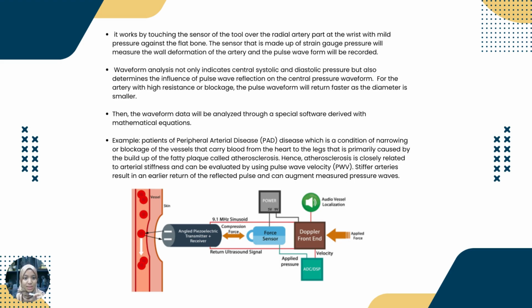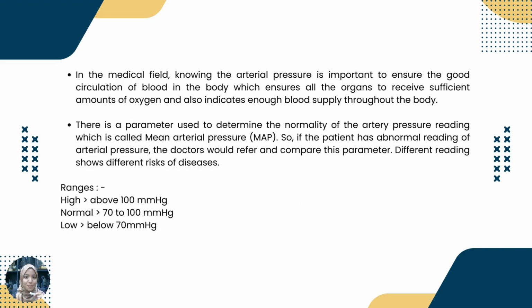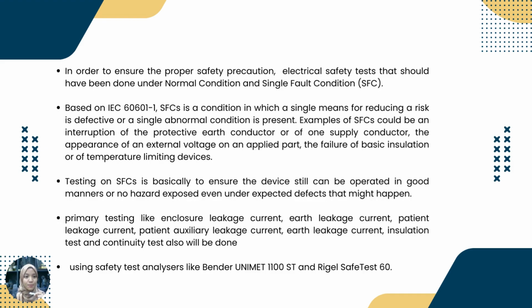For an artery with high resistance or blockage, the pulse waveform will return faster as the diameter is smaller. So, this device will be used with patients with PAD, which has a blockage of fatty plaque in their blood passage. For the medical field, knowing the arterial pressure is important to ensure good circulation of the blood. So, we use the parameter mean arterial pressure, MAP. There are certain ranges that have been fixed for this MAP. A high range indicates that a person might be exposed to cardiac or kidney failure, while a low range means that the blood circulation is not good as it does not reach enough to the major organs.